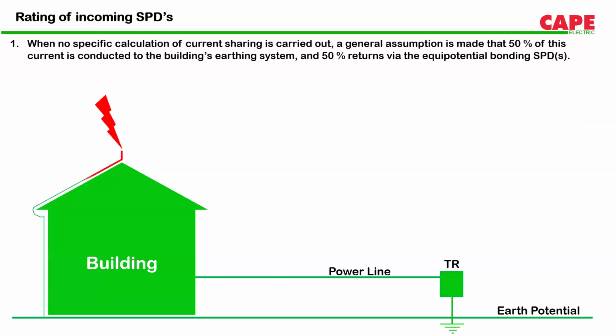One more thing a lot of people get confused about is how to select an SPD based on the rating. There are two kinds of SPDs, class 1 and class 2, as Mr. Anandu told. These are generally the two kinds of power SPDs used. The basic difference between class 1 and class 2 SPDs is the impulse current rating. A class 1 SPD shall have impulse current testing, that means lightning current testing, whereas class 2 SPDs generally do not require any lightning current withstand or testing. But the point is, how do we ensure the minimum lightning current rating in a class 1 SPD? For a class 2 SPD, you can call it zero value. You don't need lightning impulse current.